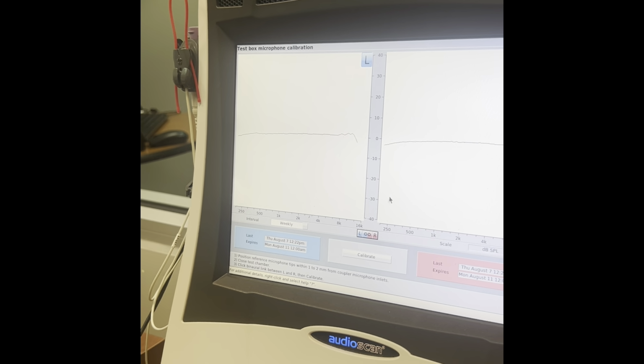Beautiful. Okay, so next we need to calibrate our on-ear ones. So if we look at the VeriFit, we're going to go to on-ear calibration. And I'm going to take the probe tubes and put them in our little guy. And we need to loop the probe tube over so that it is up like this. And then we're going to put them up here. Calibrate. Beautiful. Now we're going to do the other side and we'll leave that probe tip in there.